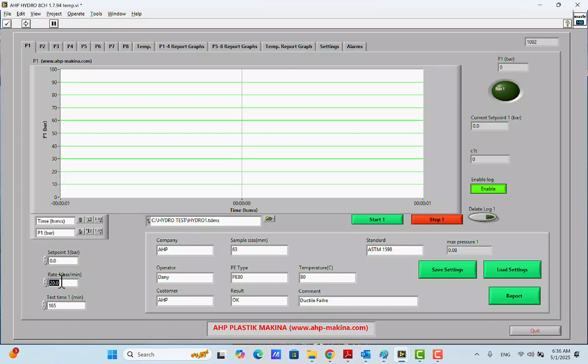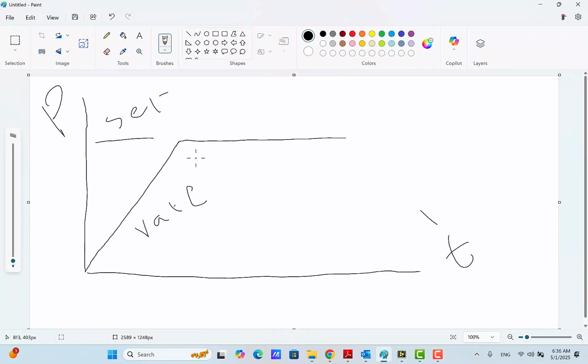This function is useful when you're going to test according to ASTM burst test of the polyolefin pipes. For example, in those cases, standard defines that the sample piece needs to be burst in the time between 60 to 70 seconds, and in that case, you can define the time. You know the burst pressure of the sample.